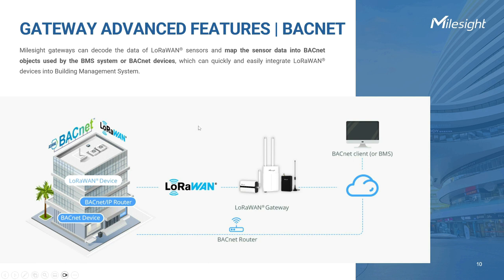In the wake of the pandemic, organizations are under intense pressure to make their buildings smarter and to manage the impact of building use on health and well-being, as well as to be more flexible about working space provision. Milesight UG67, UG65, and UG56 gateways open up pathways to achieve that. Suppose the company would like to install LoRaWAN-based room or desk occupancy sensors and indoor air quality sensors. Without the need for fixed hardwired infrastructure, the data generated by these sensors can be quickly fed into the legacy BACnet system using Milesight's LoRaWAN gateways that support the BACnet IP protocol.